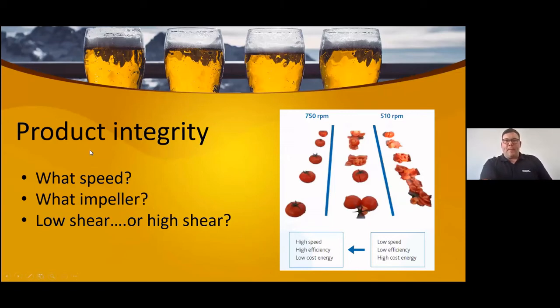It's also important when pumping to consider product integrity. There's high speed, high efficiency, low cost of energy, which goes back to Felix's question a little bit. And then there's low shear, low efficiency, high energy consumption. In this illustration, the tomatoes are still whole at the higher speed. At the lower speed, they turn to mush. In the middle, a little bit of both. So it's important what speed the pump runs at, what impeller is selected, and whether it's a low shear or a high shear application. That depends on what the pumped medium is and the different product type. But it's important that you've selected the correct pump for the correct application.